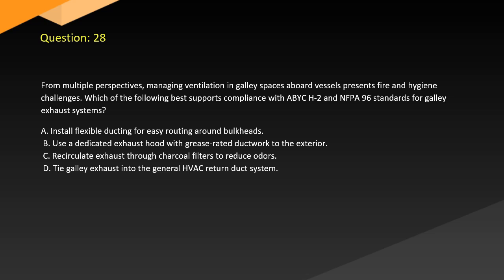Question 28. From multiple perspectives, managing ventilation in galley spaces aboard vessels presents fire and hygiene challenges. Which of the following best supports compliance with ABYC H-2 and NFPA 96 standards for galley exhaust systems? A. Install flexible ducting for easy routing around bulkheads. B. Use a dedicated exhaust hood with grease-rated ductwork to the exterior. C. Recirculate exhaust through charcoal filters to reduce odors. D. Tie galley exhaust into the general HVAC return duct system.